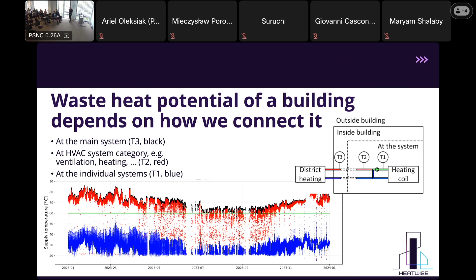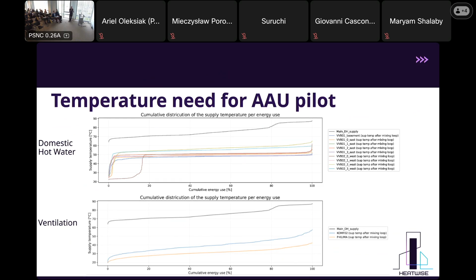Here it's divided into domestic hot water and ventilation. Domestic hot water has a fairly uniform temperature level, because we need to secure a safe temperature in the domestic hot water to avoid Legionella. So it's around 50 degrees, typically all year round, for the energy we need for domestic hot water. So if you have water of 55 or 60 degrees, that would be very good for this. If we look at the ventilation, we have 2 different ventilation systems here, running between 20 and 40 degrees, and between 25 and up to almost 60 degrees. So again, quite low temperatures compared to what we have coming into the building from the district heating network.